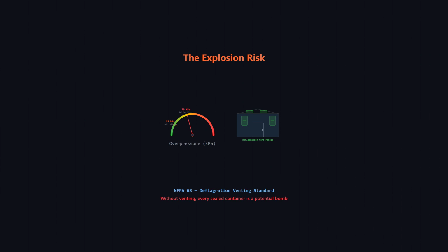The Beijing Dahongmen fire in 2021 killed two firefighters and injured one when accumulated gases inside a BESS container exploded. Overpressures exceeded 70 kilopascals, enough to destroy walls and launch debris hundreds of meters. At Liverpool, a container exploded and scattered debris 23 meters. This is why modern BESS design must include deflagration venting, engineered weak points in the enclosure that relieve pressure before it reaches destructive levels. NFPA 68 provides the calculation methodology. Without it, every sealed BESS container is a potential bomb.